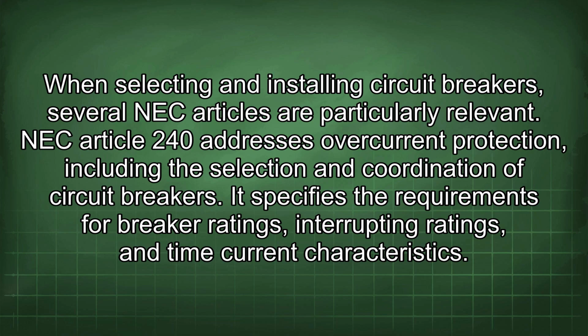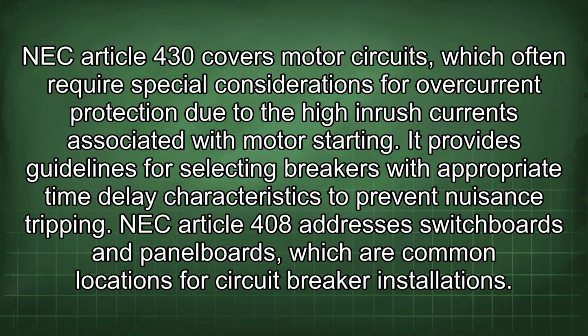When selecting and installing circuit breakers, several NEC articles are particularly relevant. NEC Article 240 addresses overcurrent protection, including the selection and coordination of circuit breakers. It specifies the requirements for breaker ratings, interrupting ratings, and time current characteristics. NEC Article 430 covers motor circuits, which often require special considerations for overcurrent protection due to the high inrush currents associated with motor starting. It provides guidelines for selecting breakers with appropriate time delay characteristics to prevent nuisance tripping.